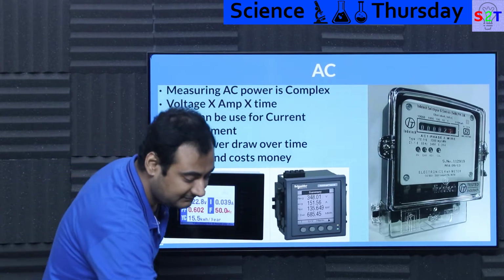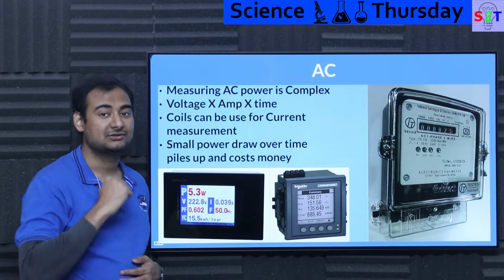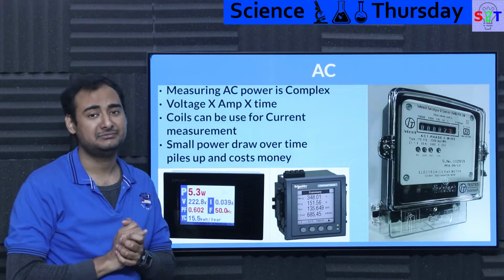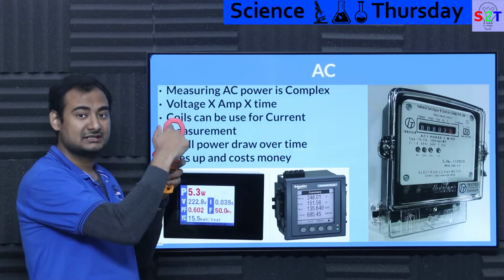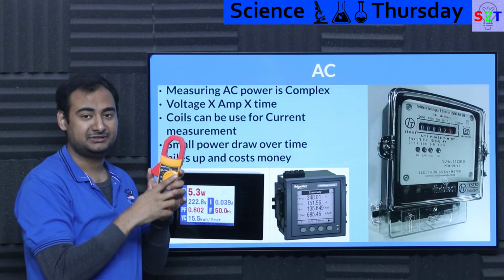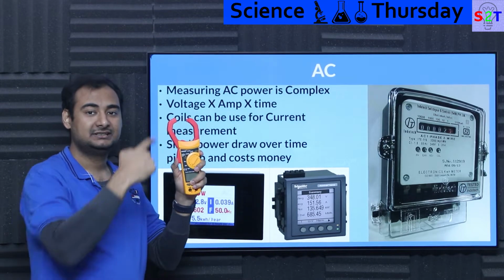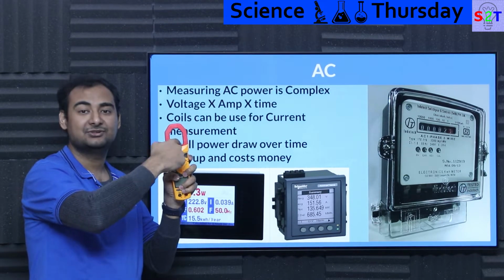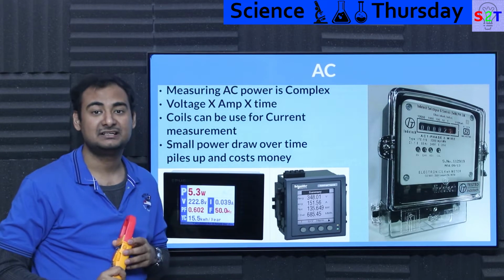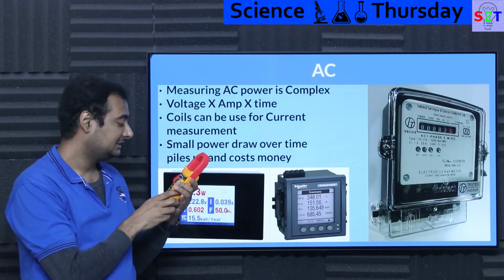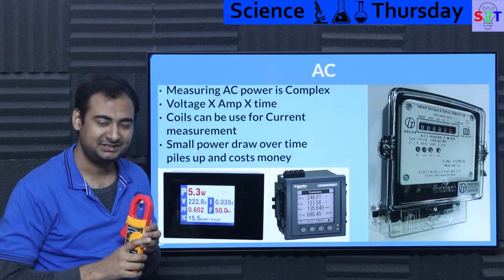The good thing about AC is that it has an alternating magnetic field. Using coils, like in this device, you can read the current just by passing the conductor through it, without worrying about limits. The small clamp meters are limited to 10 amps, but this one goes up to 1200 amps.